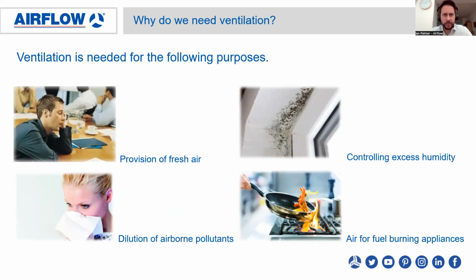So if we begin with why we need ventilation, number one is to provide fresh air into the building. Two is to dilute the airborne pollutants which are built up inside the building itself via the occupants and the fabrics of the building. Three, we need to control excess humidity in the wet room areas to avoid mold growth. And four, providing air for fuel burning appliances. So these are some of the main reasons why we need ventilation in any building, really.